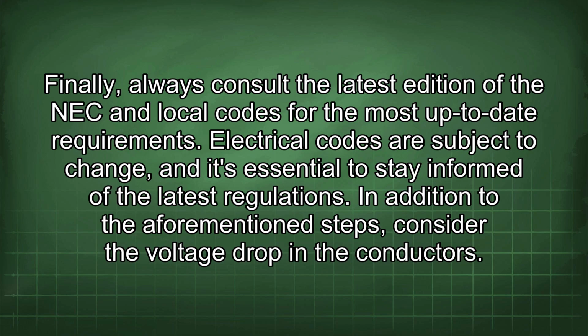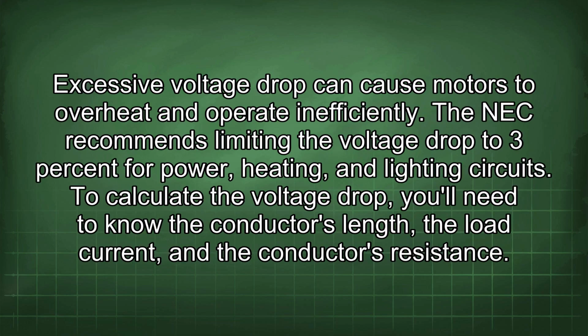In addition to the aforementioned steps, consider the voltage drop in the conductors. Excessive voltage drop can cause motors to overheat and operate inefficiently. The NEC recommends limiting the voltage drop to 3% for power, heating, and lighting circuits.